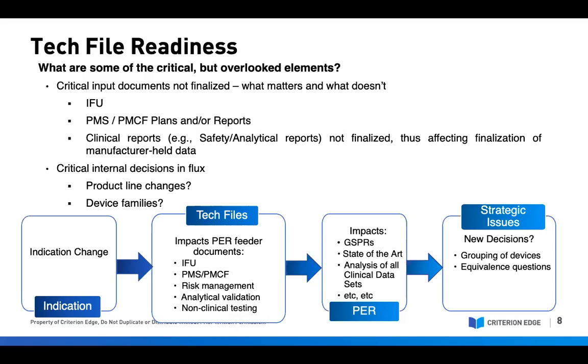I thought I'd include a cause-effect scenario that arises out of a manufacturer decision that leads to changes in a tech file document. So there's been a strategic regulatory decision made to change the indication of an IVD and to get it approved as part of the upcoming IVDR update. That indication change impacts many critical documents that feed directly into the PER, such as the IFU, PMS, and risk management, and may even require possible updates to non-clinical and design validation documents. In this scenario, the impact really to the PER is global.